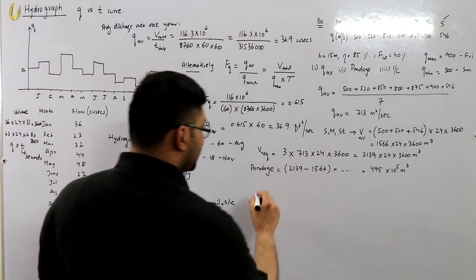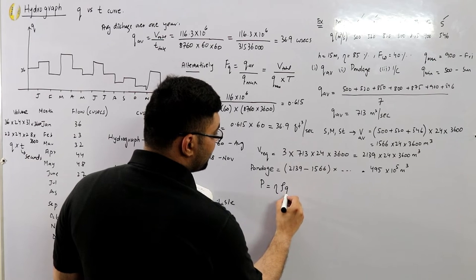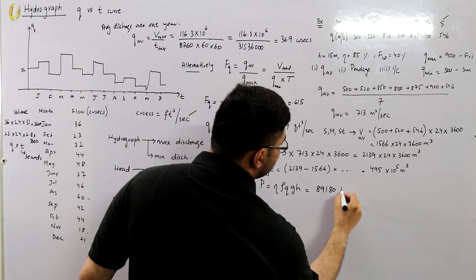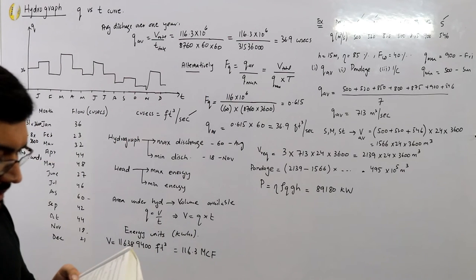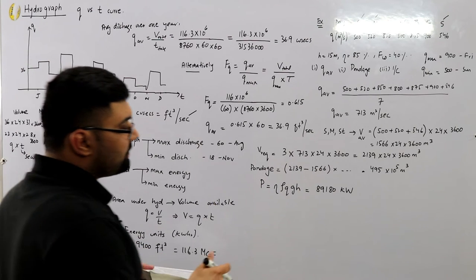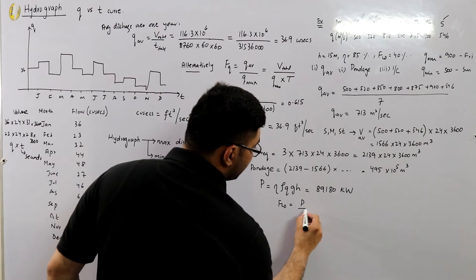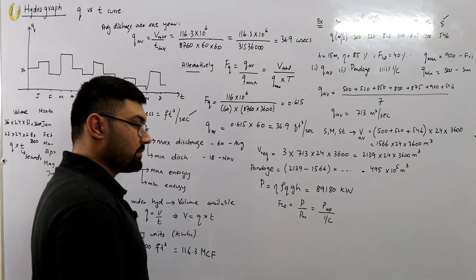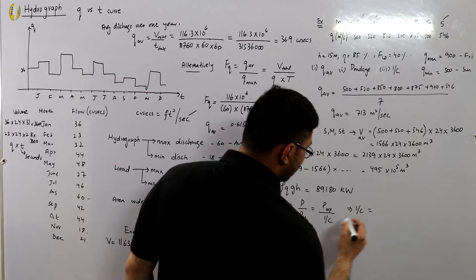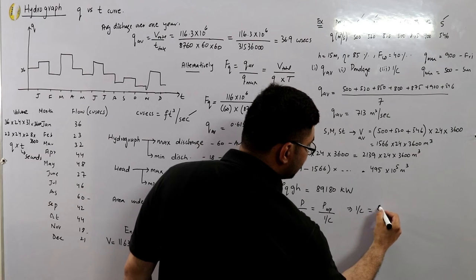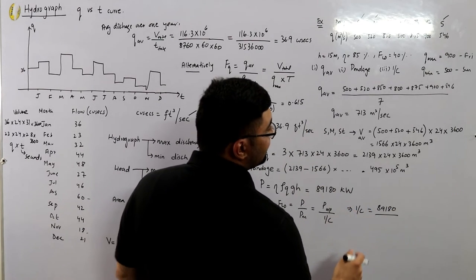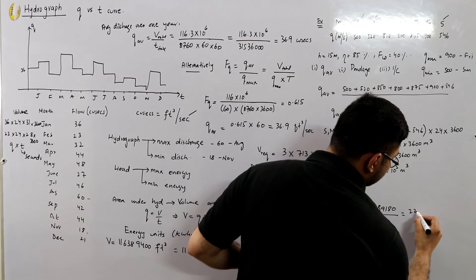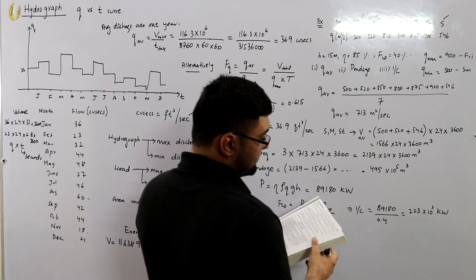For the installed capacity, the output power is: P = η × ρ × Q × g × h = 89,180 kilowatts. The load factor equals average power divided by maximum demand (installed capacity), so: installed capacity = output power / load factor = 89,180 / 0.4 = 223 × 10³ kW = 223 megawatts.